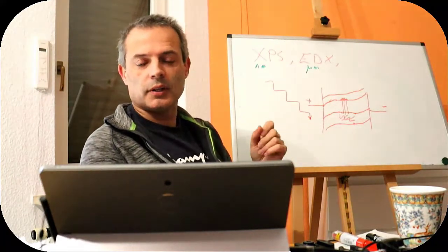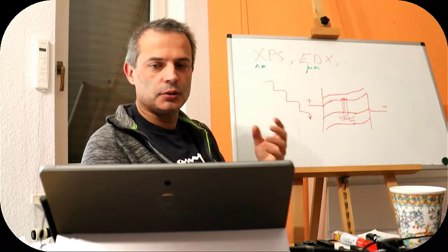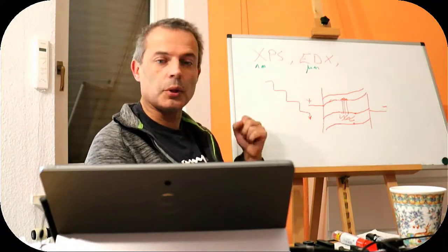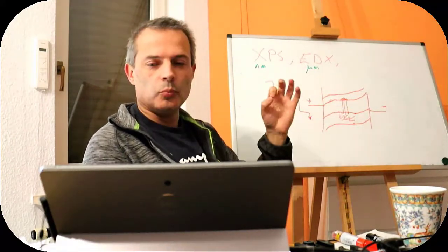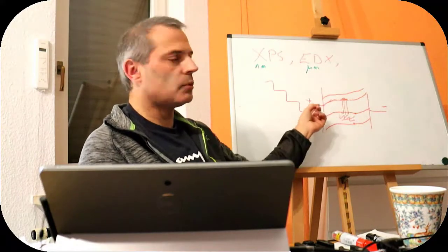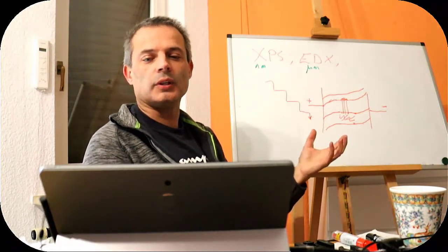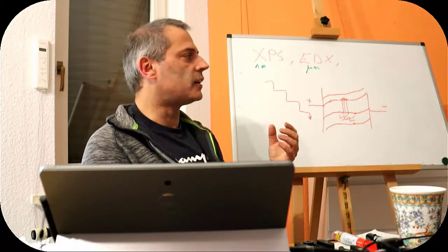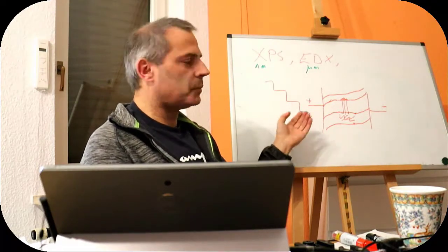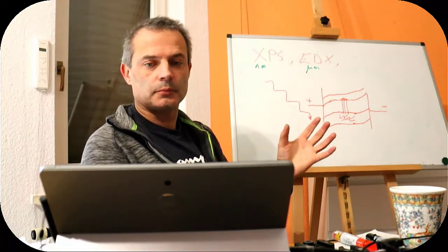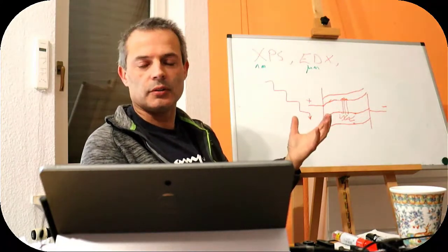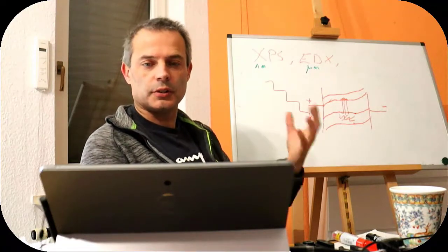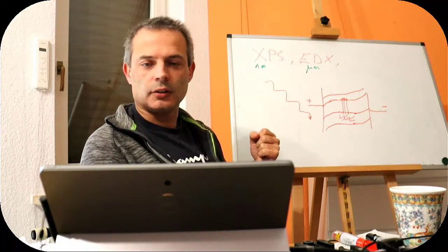The issue that you may already have noticed is that if two X-ray photons hit within enough time that the charge hasn't run out, then I will get the wrong energy. What this means practically is that I cannot have so many photons coming out that this happens too often. Otherwise I will end up with too dirty data and it is impossible to clean it up. There are several ways to improve it, physical ways and computer ways.